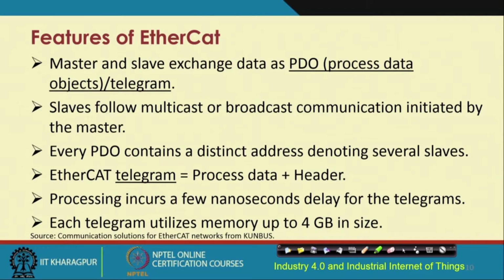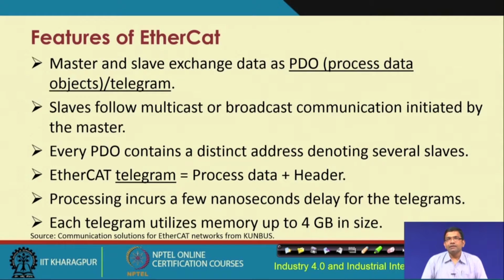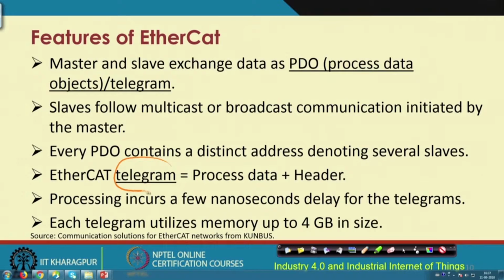Here also it uses the master slave protocol for data exchange between the client and the server, and this is done in the form of something known as the PDO, the process data object. It is also known as the telegram. In EtherCAT, the telegram is defined in this manner: the process data plus the header together form the telegram or the PDO. Going back, I said that it is master slave communication. The slaves will follow multicast or broadcast communication, and every PDO contains a distinct address denoting the several slaves. Every telegram basically utilizes memory up to 4 gigabytes in size in EtherCAT.